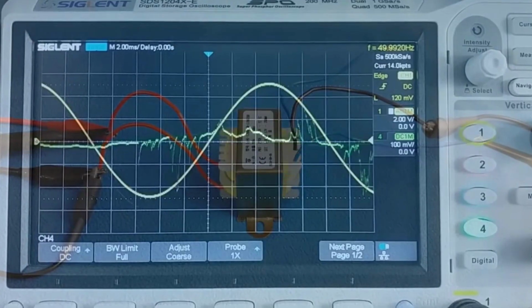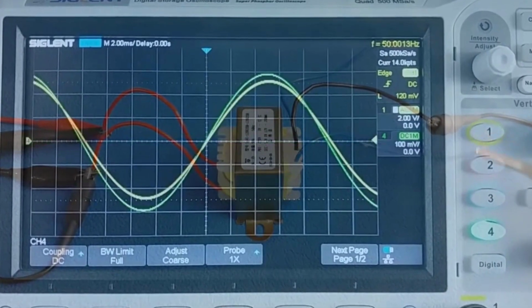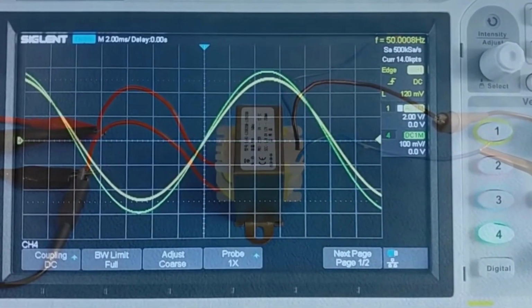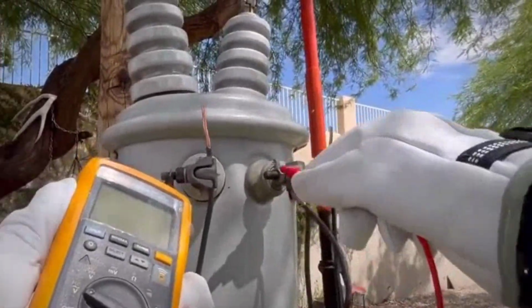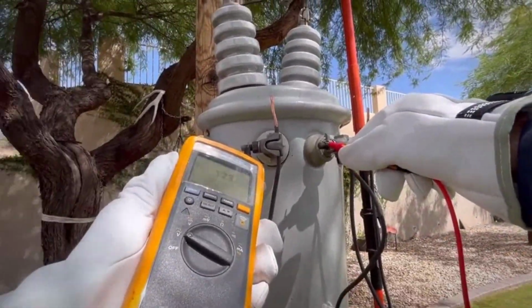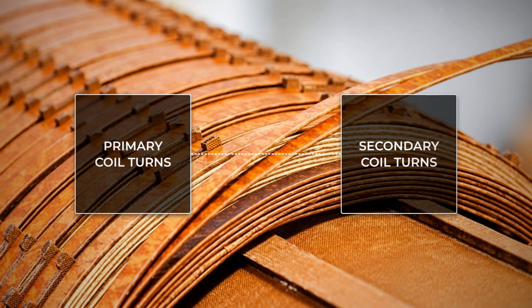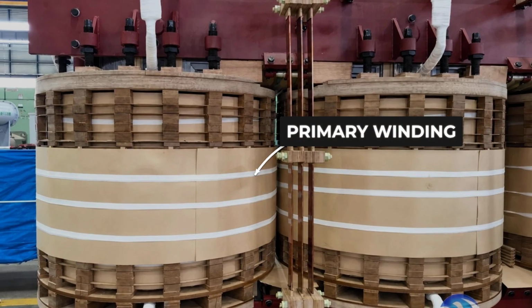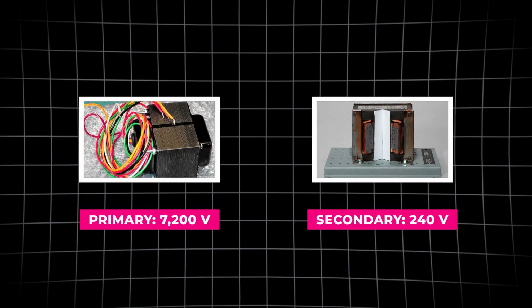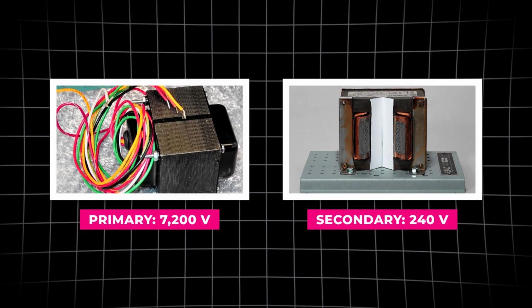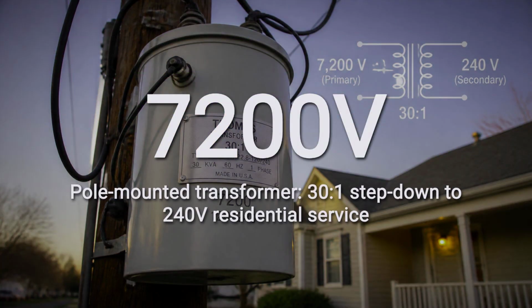As this changing magnetic field sweeps across the secondary loops, it forces electrons to move, inducing a current inside the secondary winding. This voltage reduction depends on the count of loops in each coil. With thousands of turns on the primary side and far fewer on the secondary, the voltage drops proportionally. A common 30-to-1 ratio safely reduces 7,200 volts down to 240 volts.